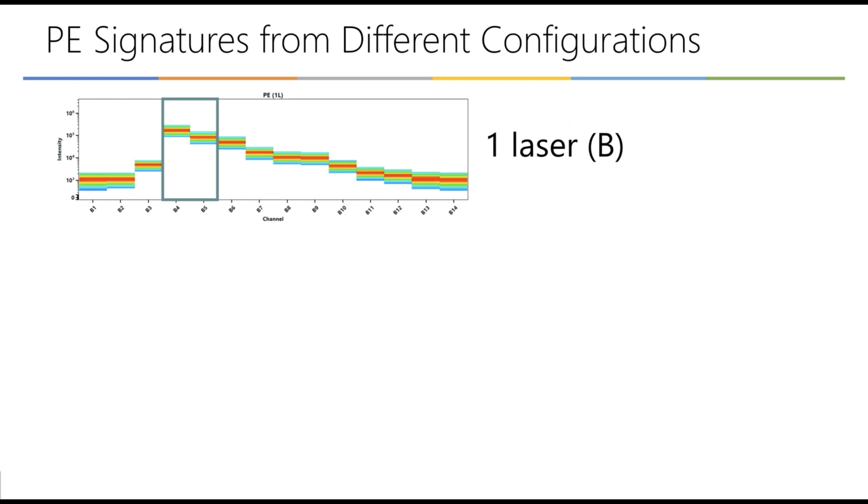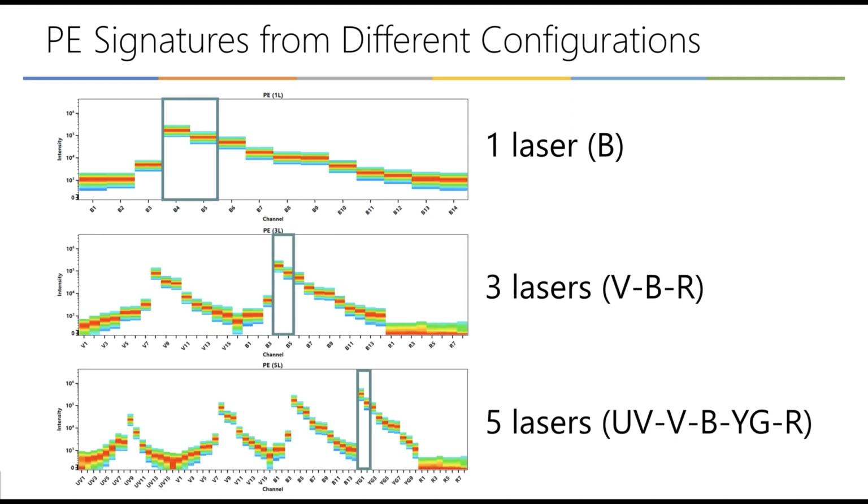This single laser blue spectral plot most closely resembles the PE emission profile that I showed you on the previous slide, with the box channels outlining the portion of the spectrum that's characterized by a conventional cytometer. Observe that when we characterize the PE emission from every laser on the system, we gain a lot more information about how PE is emitting fluorescence, and correspondingly, how this fluorochrome is likely to contribute spread into other fluors in a multicolor assay.